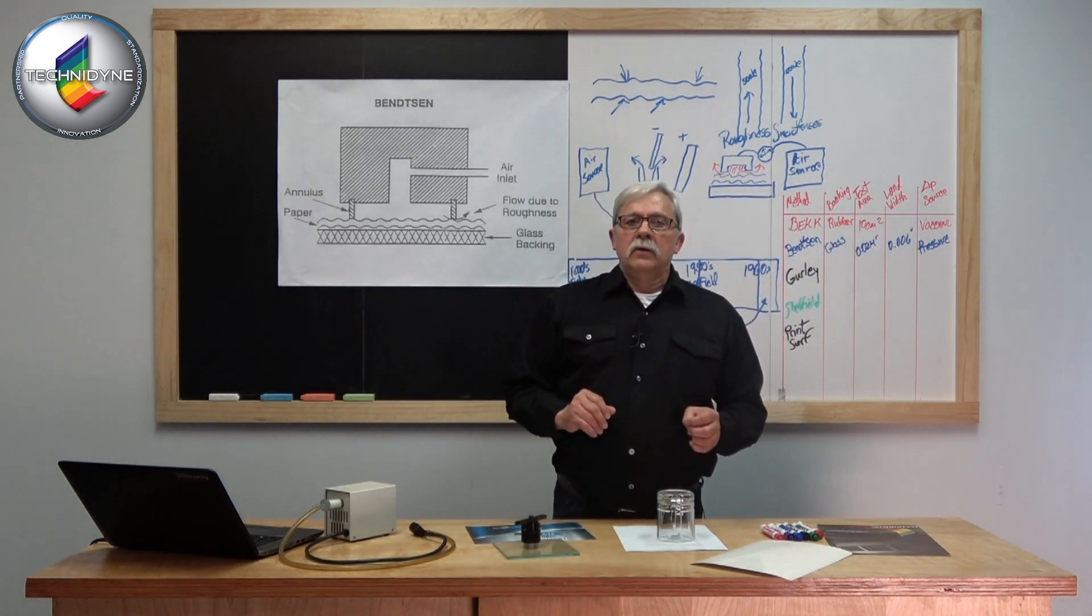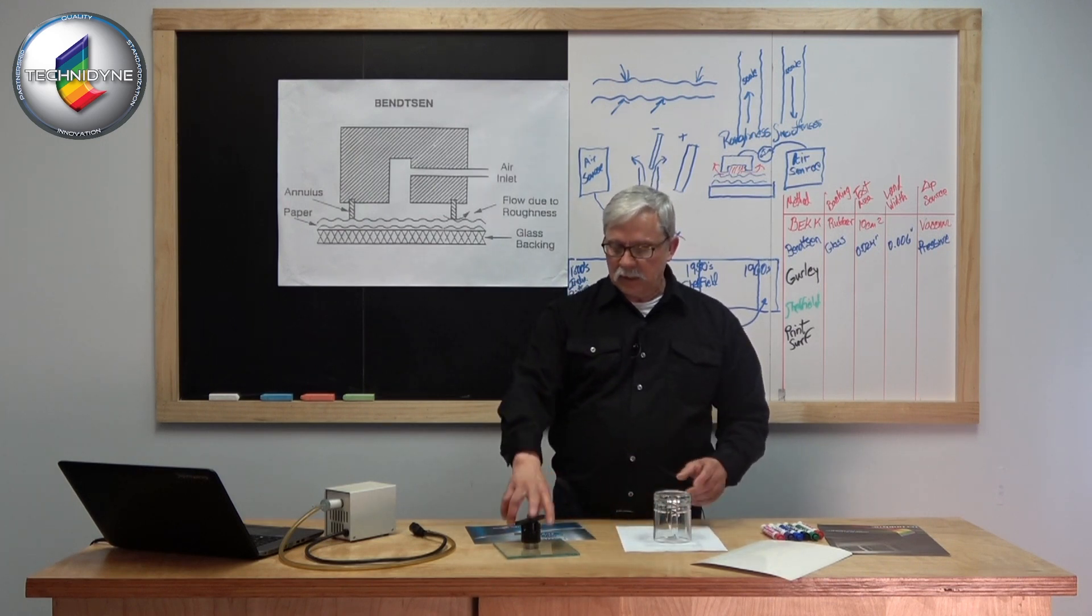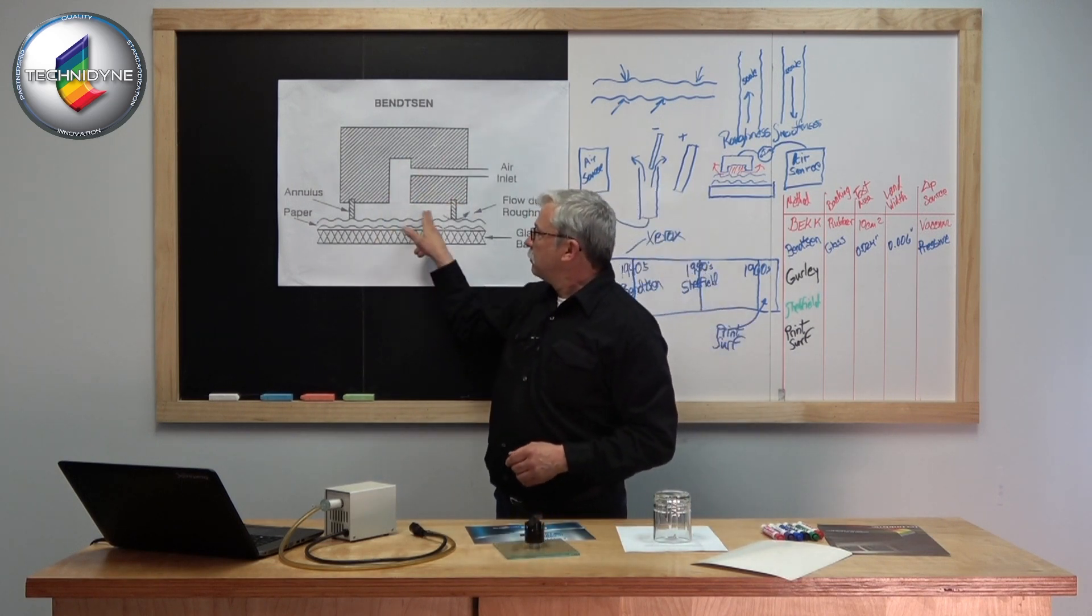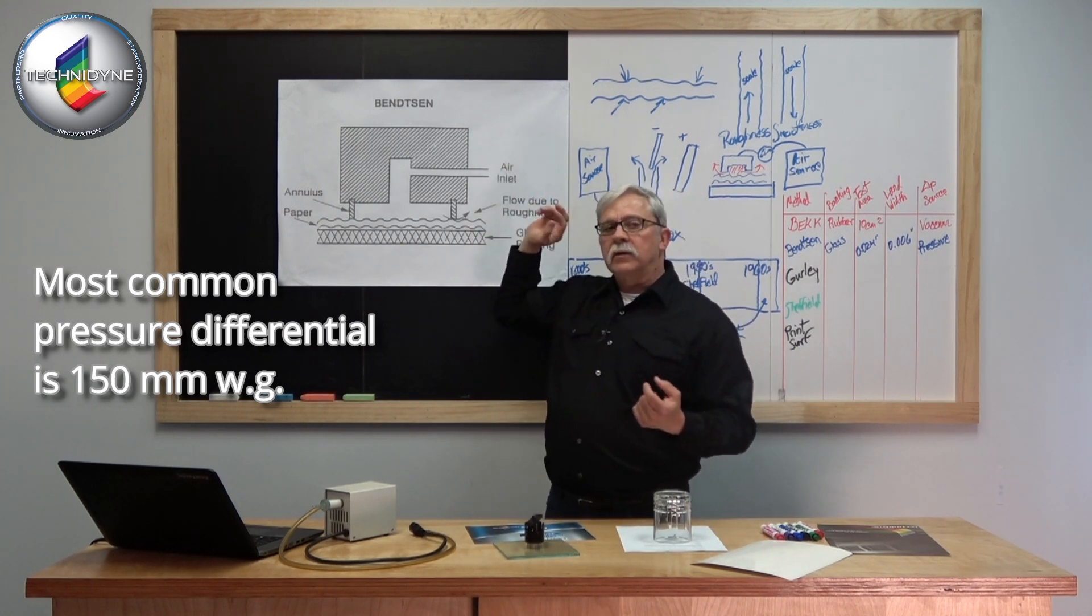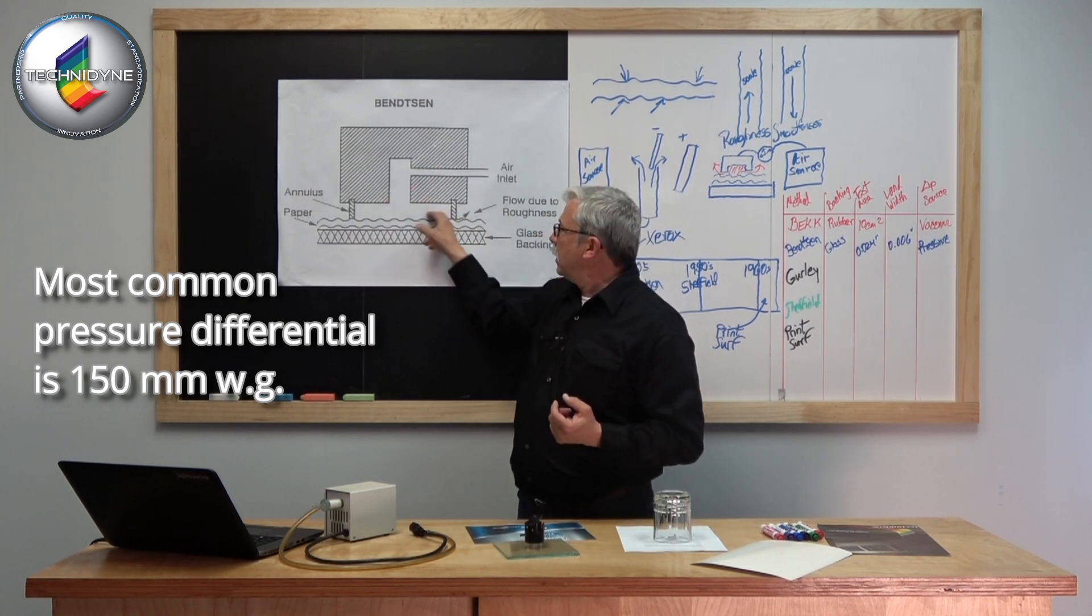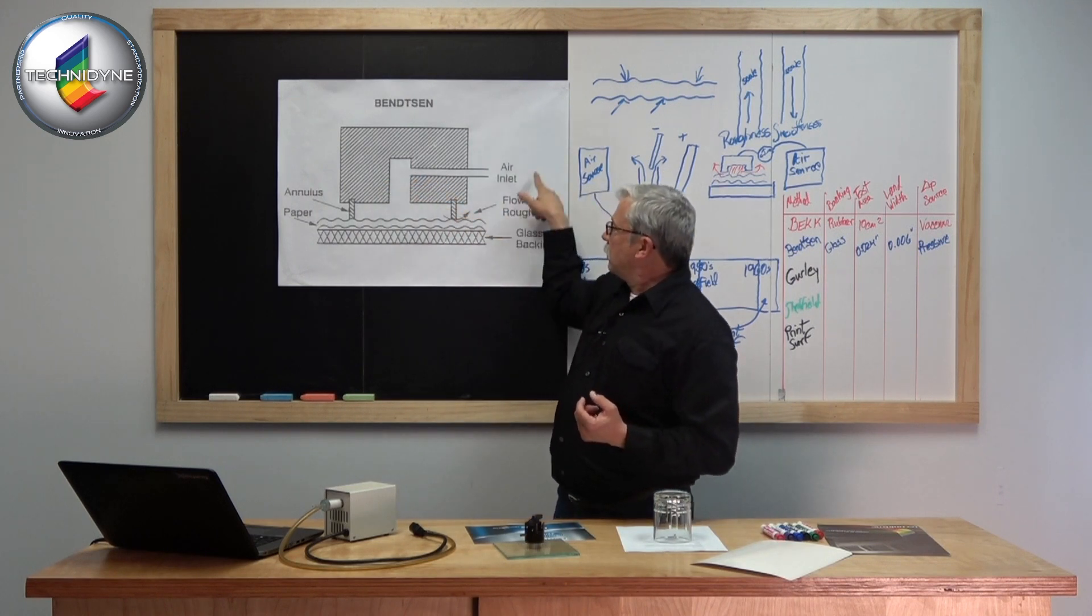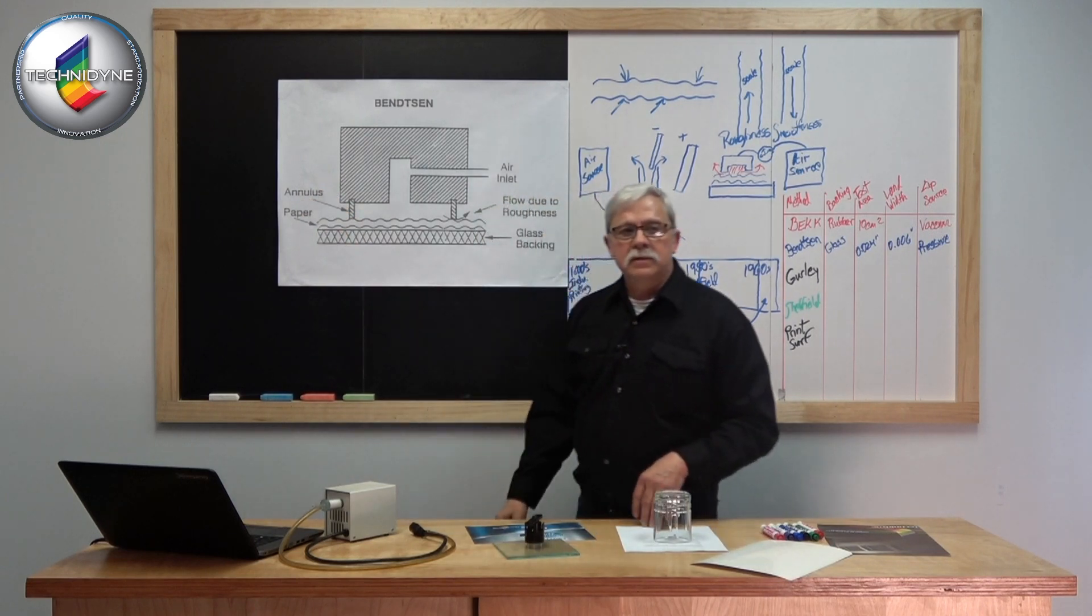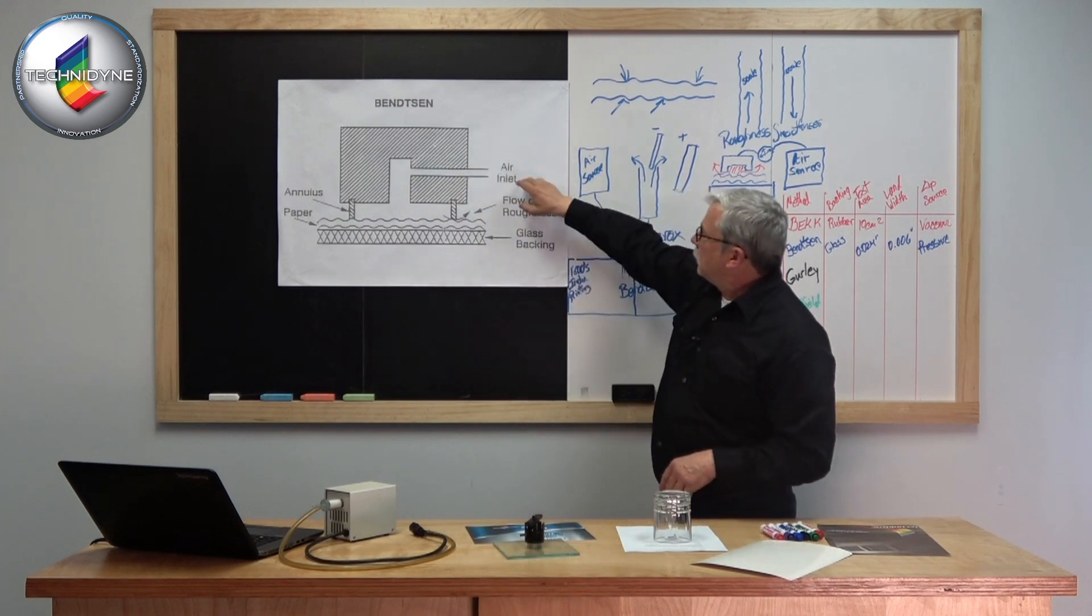Much like the discussion I had earlier, they took this idea to pressurize this cylinder underneath the measurement piece, pressurize it to a fixed starting pressure. If they could continually feed air underneath this captured area, they could accurately measure the air that leaks out underneath these metering lands.